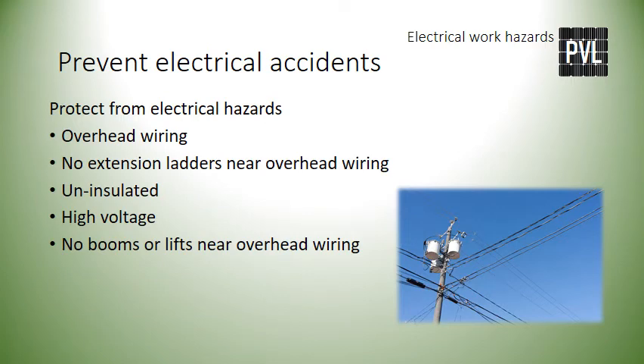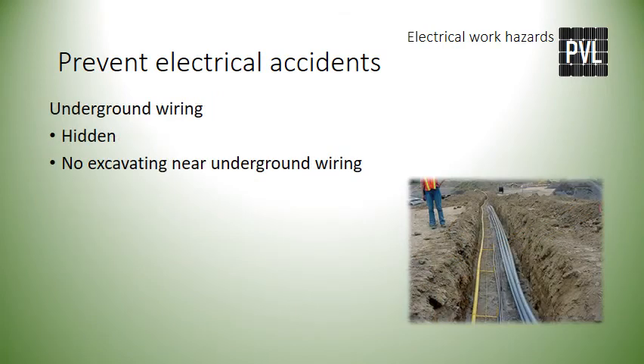Overhead wiring is likely located outdoors and often carries high voltages. Never use extension ladders near overhead wiring. Never use poles or other far-reaching equipment or tools near overhead wiring. Lift or boom vehicles are especially dangerous to operate near overhead wiring. The likelihood of electrocution is high if you come in contact with overhead wiring, since it is often uninsulated without a protective jacket. There are various recommended distance requirements when working near various types of overhead wires — consult the NEC if this type of work is necessary.